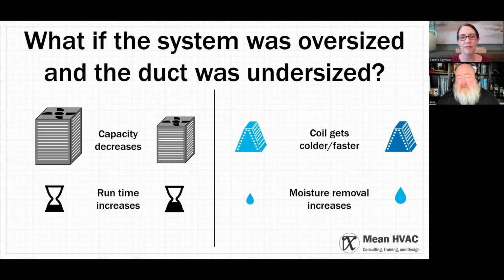That happens a lot with an existing system that's oversized and underducted. When you don't get enough air through your system, it no longer has as much capacity. So on the label it's this big thing, but in your house it's not as big, it's not working as well because we're starving it of airflow. And that means it's going to run longer.